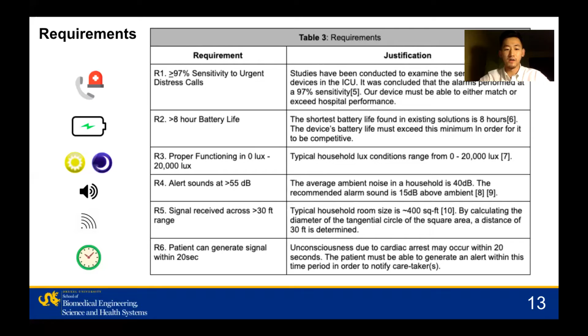The alert must sound at greater than 55 decibels, and the alarm signals must be received throughout at least a 30-foot range. The range of the alarm must exceed this in order to avoid limiting the caretaker and also avoid failed signal generation. It is important that the patient is able to generate a signal within 20 seconds of distress, since a patient may lose consciousness under cardiac arrest in 20 seconds.